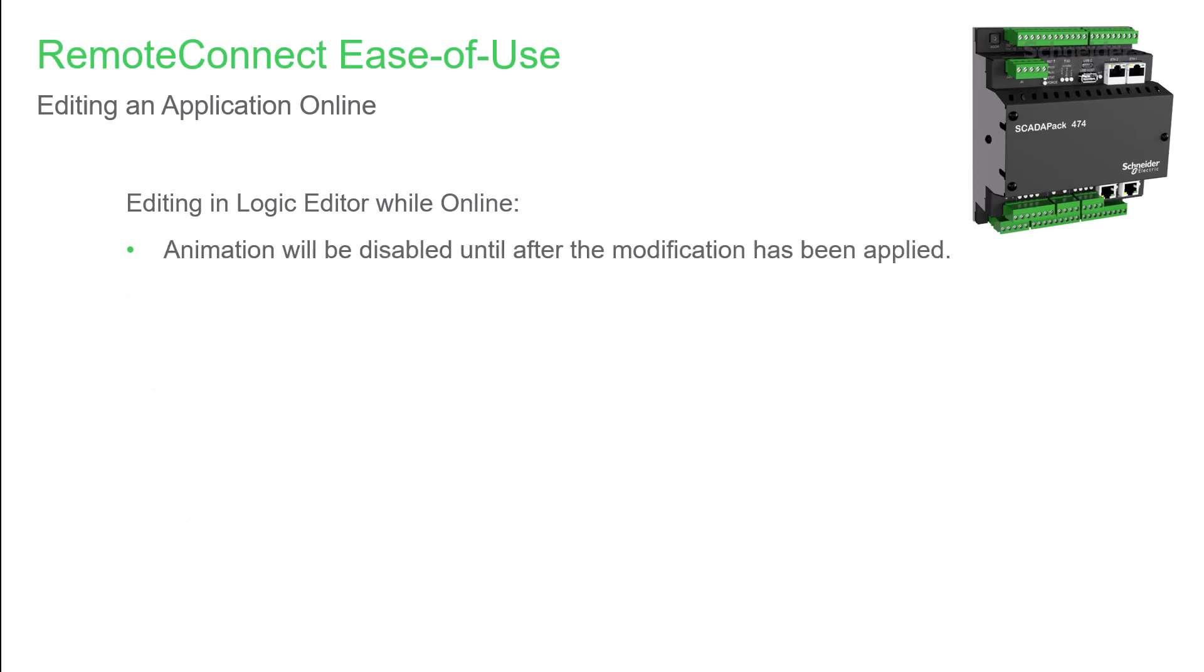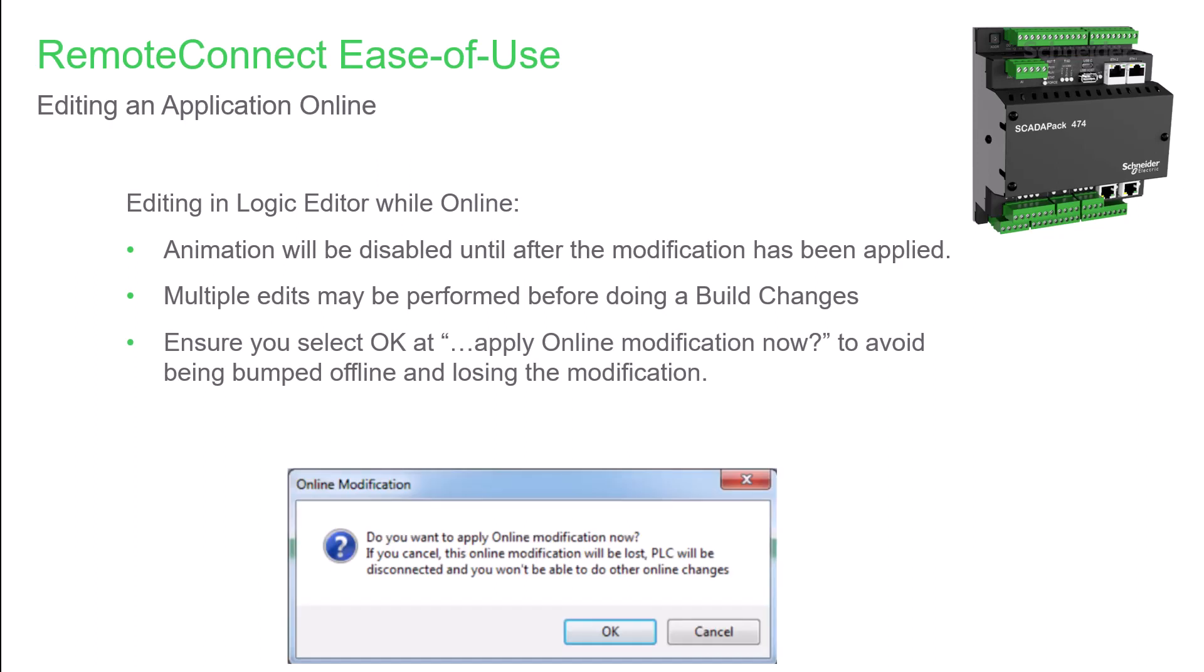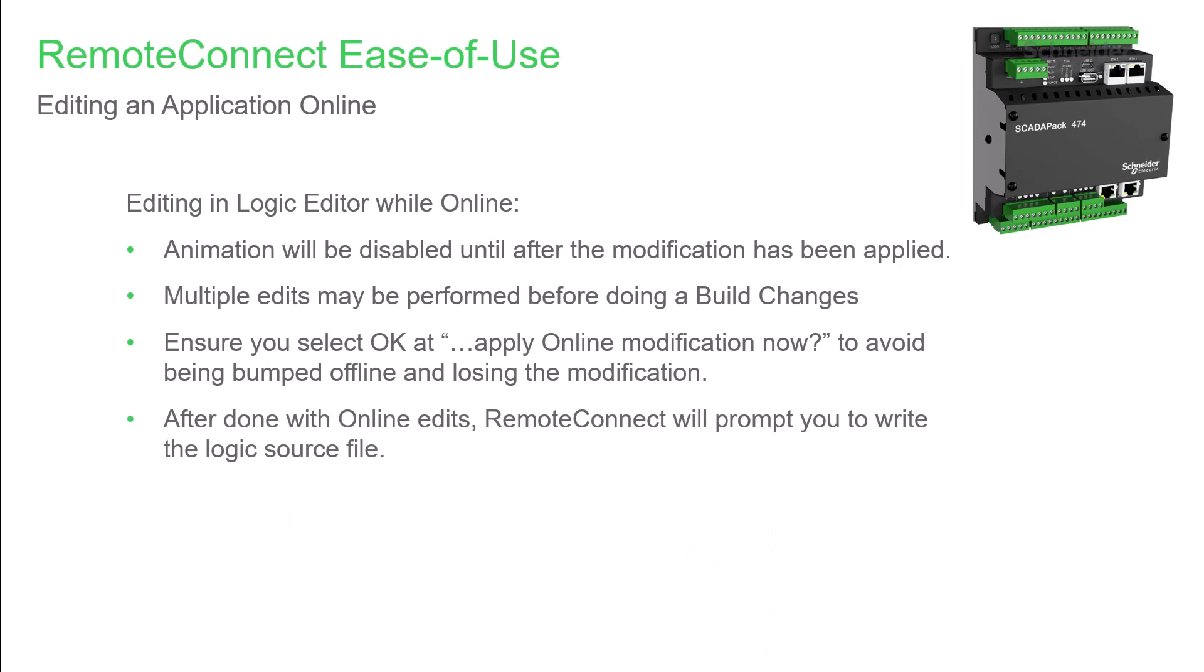A few pointers to consider when doing online editing. First, after you confirm a modification, you'll see that any animation in the logic section is disabled until after the edit is complete. There's no need to build changes with every edit made. You can make multiple edits, and then build changes when you're done. Remember to select OK at the prompt, 'Do you want to apply online modification now?' Clicking Cancel will bump you offline, and your edits would be lost. And after you're done with online edits, RemoteConnect will prompt you to write the Logic source file. You can do it at that time, or choose to do it later, if you'll be doing more editing.